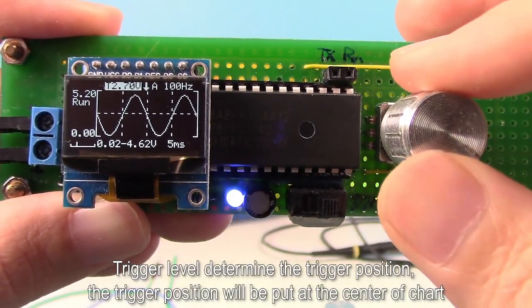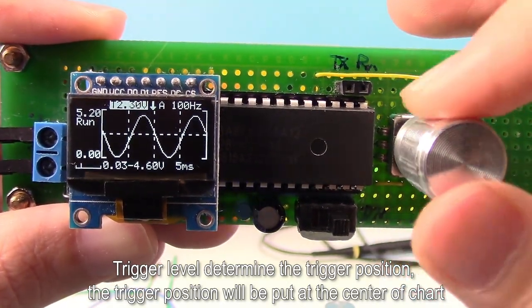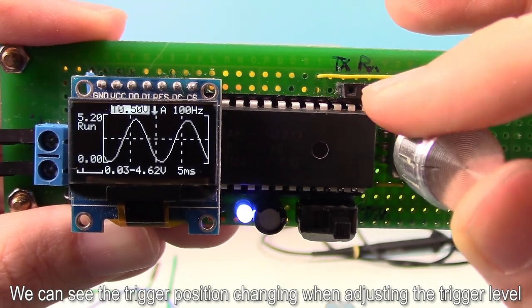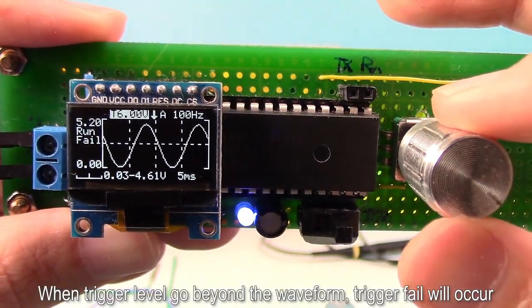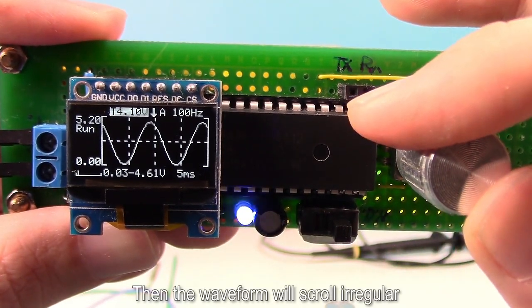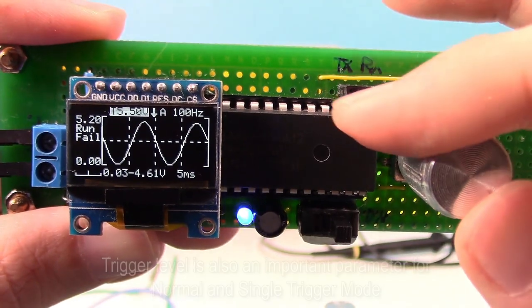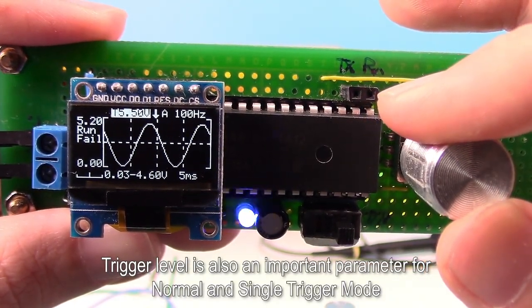Trigger level determines the trigger position. Trigger position will be put at the center of chart. We can see the trigger position changing when adjusting the trigger level. When trigger level goes beyond waveform, trigger fail will occur. Then the waveform will scroll irregularly. Trigger level is also an important parameter for normal and single trigger mode.